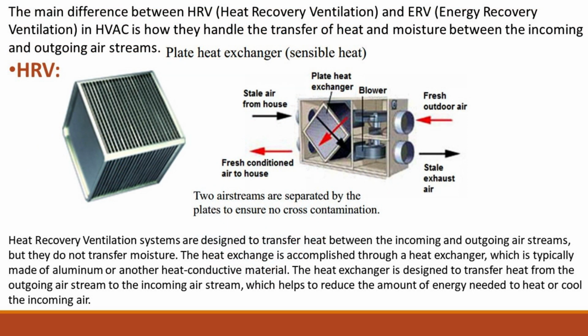Let's start. The main difference between HRV, heat recovery ventilation, and ERV, energy recovery ventilation, in HVAC is how they handle the transfer of heat and moisture between the incoming and outgoing air streams. HRV, heat recovery ventilation systems are designed to transfer heat between the incoming and outgoing air streams, but they do not transfer moisture. The heat exchange is accomplished through a heat exchanger, which is typically made of aluminum or another heat-conductive material. The heat exchanger is designed to transfer heat from the outgoing air stream to the incoming air stream, which helps to reduce the amount of energy needed to heat or cool the incoming air.